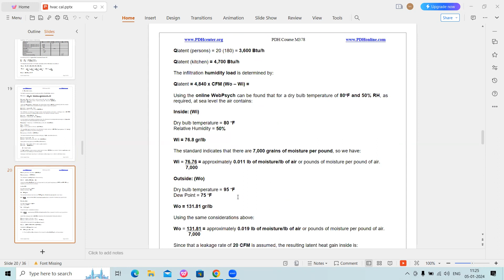So what are the components generally there in our latent heat loads? Latent heat simply means it is also a kind of heat, but it increases the moisture of air. So by our particular usage components, for light activity, people produce latent heat also. That latent heat happens through their respiration system. So that is 180 BTU per hour per person. Let me find out that value: per person 180, and 20 persons are there.